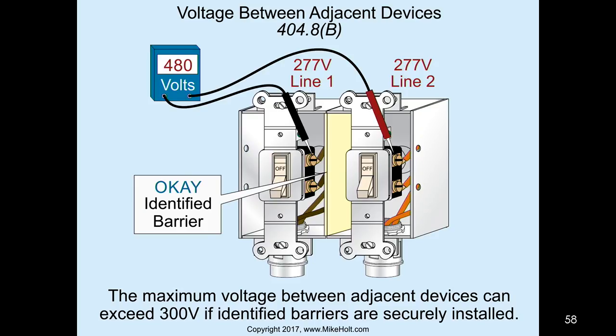Now, the easy thing though is this. Anytime you have 277/480 volt systems, and you have multiple switches in the box, I don't care what the deal is, you have to have barriers between all the switches. No matter what. But because, see, you have 277. Look at the next graphic here. So that case is 277.